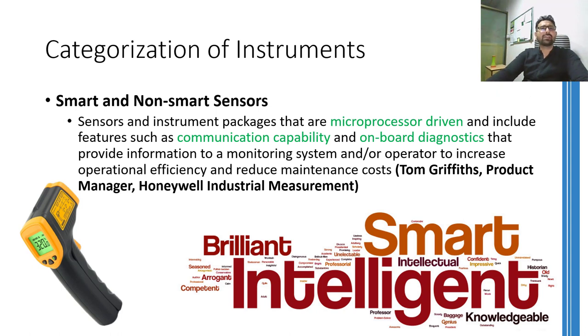Secondly, it should have communication capabilities for transmitting its signal to some control or monitoring system. And thirdly, it should have some form of onboard diagnostics that allow it to reduce maintenance costs and increase operational accuracy. Therefore, any measuring system incorporating these features may be regarded as a smart sensor or a smart measuring system. Keep in mind that a sensor that only sends its data to some remote location is not a smart sensor.